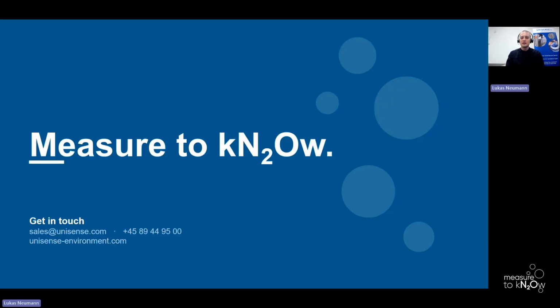So just to wrap it up, it's the same nitrous oxide sensor with a new system. It's the same Clark-type electrochemical sensor with the same validated emissions calculations, but rebuilt around how you actually prefer to work with the data. So in the broad scheme, you will spend less time at the controller and more time at the plant. We have better diagnostics. The sensor will tell you when it needs you, and it scales with your plant, up to 16 sensors, 1 console, 1 data stream to your SCADA.